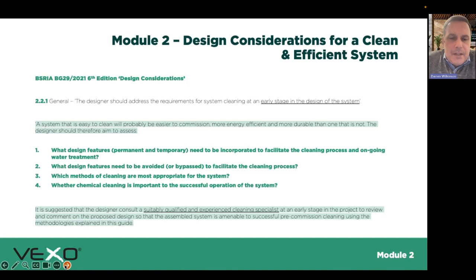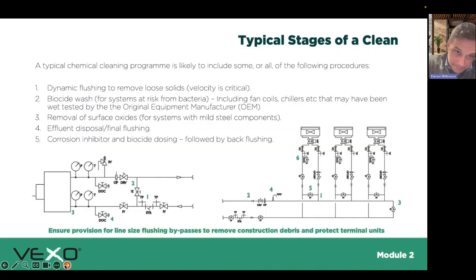It may be that there needs to be some valves arranged for a temporary hose to be installed because you're connecting to an existing chiller, and maybe you don't want to leave a hard pipe temporary bypass. You want to use something temporary. Also which things need to be bypassed, what methods of cleaning are appropriate for the system, and sometimes whether cleaning is important to be successful. You might have a small system and it's all stainless steel pipework, and it's, do we really need to go through that? So engage early on, certainly with a specialist, would be my advice.